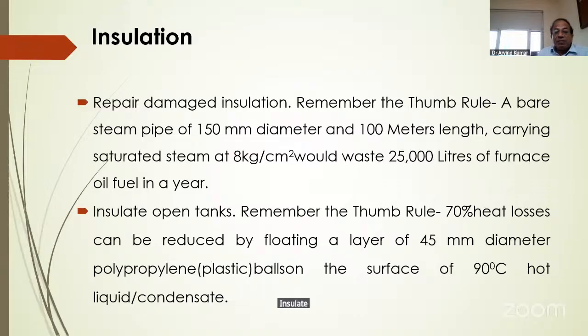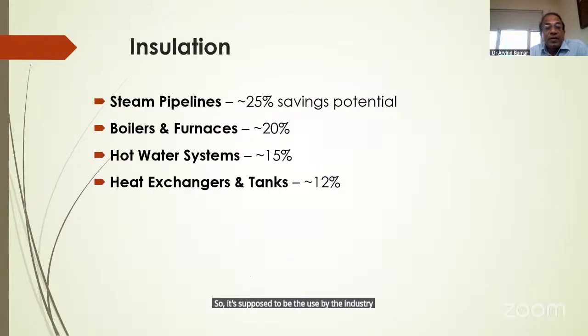Insulate open tanks. Remember the thumb rule: 70% of heat losses can be reduced by floating a layer of 45 mm diameter polypropylene balls on the surface of 90 degrees centigrade hot liquid condensate. That is a major factor we can use in industry. Steam pipelines have the potential of saving 25%, boilers and furnaces 20%, hot water systems 15%, and heat exchangers and tanks 12%.